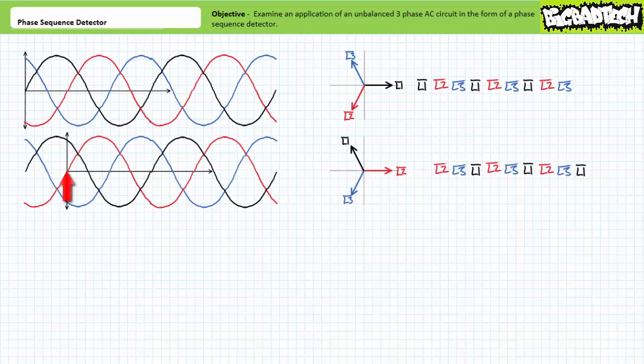Consider L2 in red as the reference. Represented as phasor equivalents with phase L2 assumed to be the reference, L2 in red would be 120 volts at an angle of zero degrees, L3 in blue would be 120 volts at an angle of negative 120 degrees, and L1 in black would be 120 volts at an angle of 120 degrees. Given L2 is established as our frame of reference, we can state L2 peaks, then L3, then L1. When extended for another cycle, the sequence again repeats itself: L2, L3, L1. Given the repetitive nature of these waveforms, the choice of reference has not changed the phase sequence, only the starting point within the same sequence.